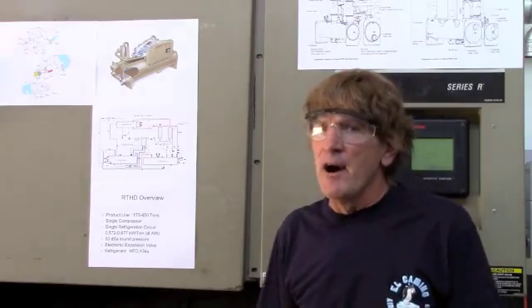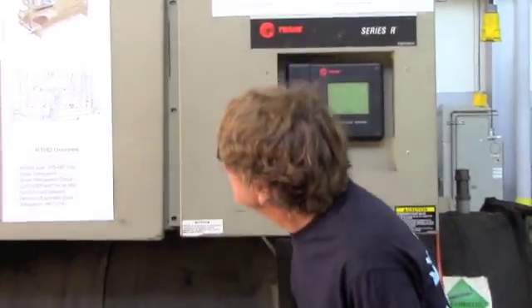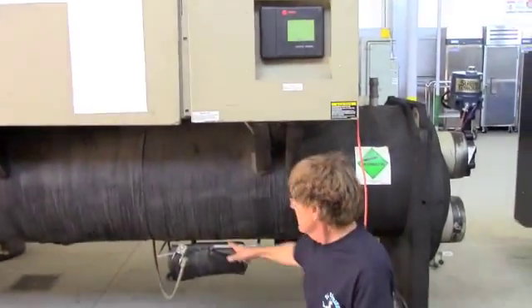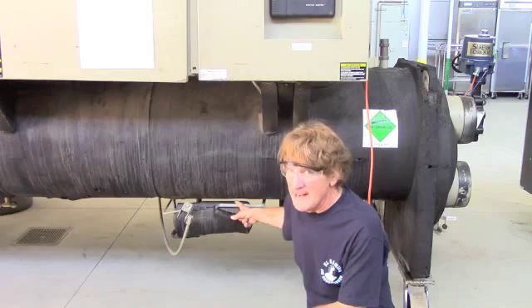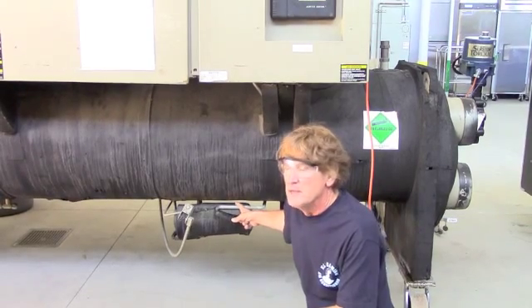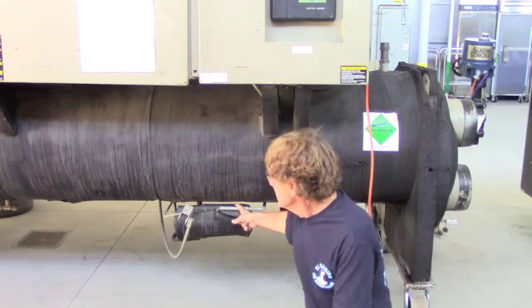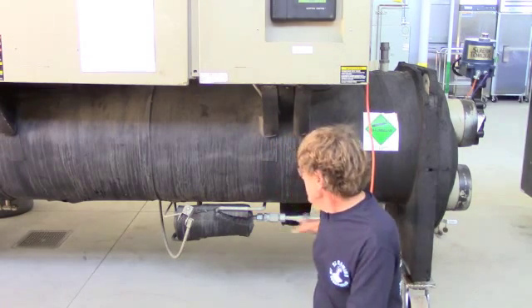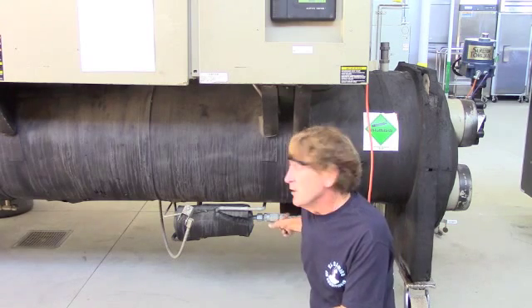If we look down in the bottom here, this is called a gas pump. This gas pump has a single purpose, to recover oil from the bottom of the evaporator. So what happens is, we have a line here. It allows both refrigerant and oil to come in here.